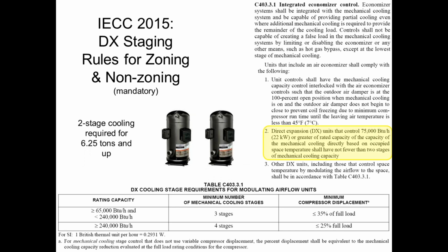So the first one is DX units that have integrated economizers that are above 75,000 BTUs have to have no less than 2 stages of capacity. Well, anything above 54,000 has to have an integrated economizer. So essentially what this is saying, if you're above 75,000 BTUs, you have to have 2 stages. You cannot put in a 1-stage 10-ton unit anymore. I know people do this. It was always stupid before. It's still stupid now, but the code doesn't allow you to do it. So 75,000 BTUs is essentially anything more than 6 tons is going to have 2 stages of cooling minimum. And everyone reads that, interprets it the same way, and everyone's pretty logical on that. There's been no debates or arguments at the state level.